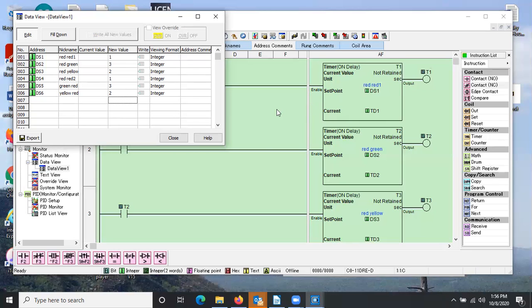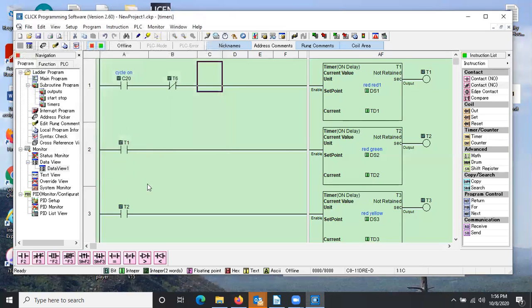On the outputs, when you go to the output rung, remember you want lights on while the timer's timing, which means, we'll close this. So if timer 2 is, I want the timer timing logic, I need the logic that turns it on. Any logic here, which we only have T1, and I need to have T2 is examine off, or this normally closed contact right there. That will be my timer timing logic. And that's what I use to turn on my outputs at the certain times that I want.